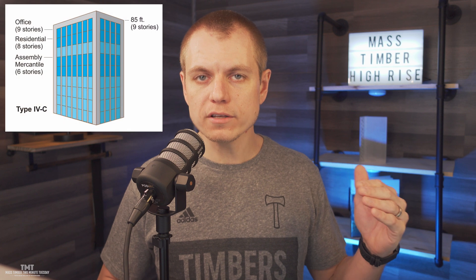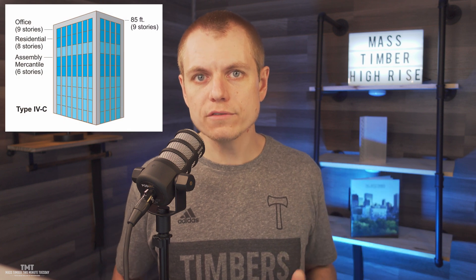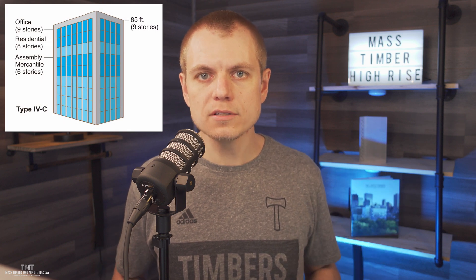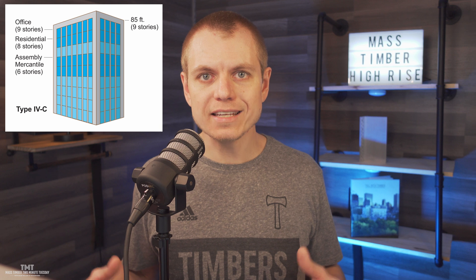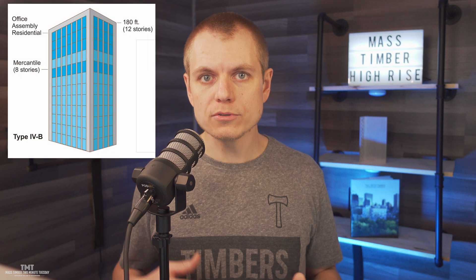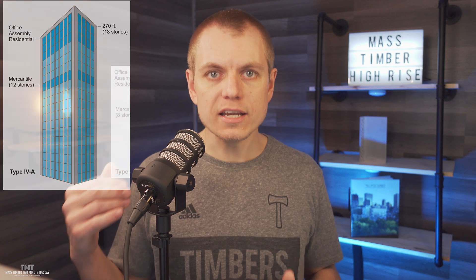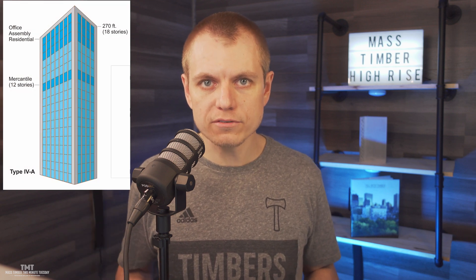Looking at the new construction types in the 2021 IBC for tall mass timber construction: type 4C allows you to go up to 8 stories for multifamily occupancy, or 9 stories for business occupancy, both limited to 85 feet from grade to roof. Type 4B construction allows up to 12 stories and 180 feet, and type 4A construction allows up to 18 stories or 270 feet.